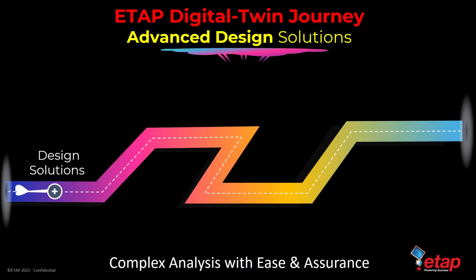Let's now continue with advanced design solutions and more complex analysis. Number one, time series unified load flow analysis, used in renewable studies where generation output is highly variable and demand data is available from historic measurements. Solve unified power flow taking into account both AC and DC networks over a function of time and produce load duration curves. Number two, transient motor starting. Calculate actual acceleration time and analyze the impact on the rest of the system, including the ability to compare between multiple motor starter types.